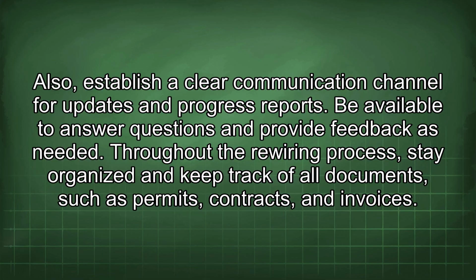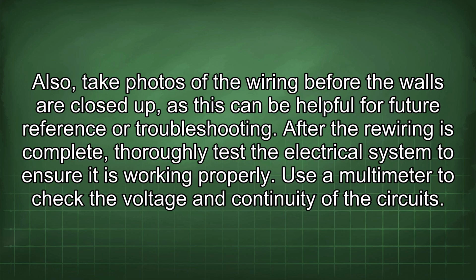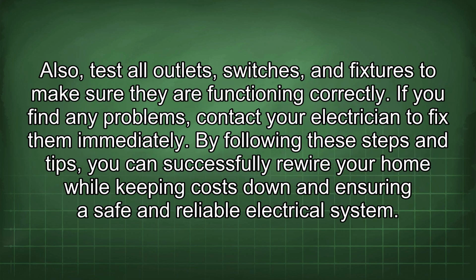Throughout the rewiring process, stay organized and keep track of all documents such as permits, contracts, and invoices. Also, take photos of the wiring before the walls are closed up, as this can be helpful for future reference or troubleshooting. After the rewiring is complete, thoroughly test the electrical system to ensure it is working properly. Use a multimeter to check the voltage and continuity of the circuits. Also, test all outlets, switches, and fixtures to make sure they are functioning correctly. If you find any problems, contact your electrician to fix them immediately.